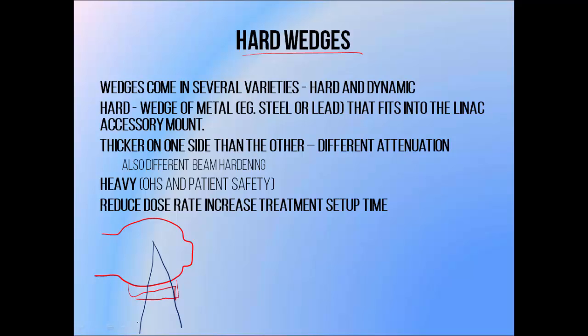Whenever we pass the beam through a filter it affects the energy spectrum. Because some parts of the beam pass through thicker pieces of the filter than others, different parts of the beam are hardened to different degrees. In this case, a longer path through the metal filter results in more hardening, so the beam winds up with a higher energy on one side than the other.